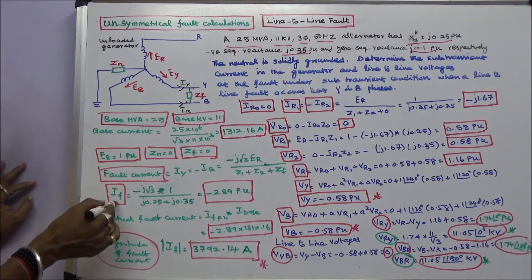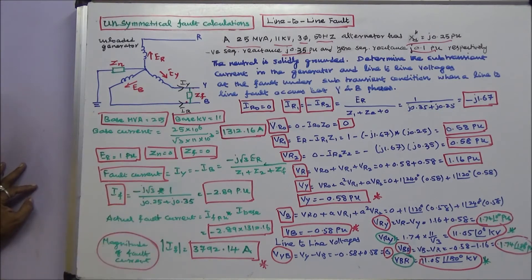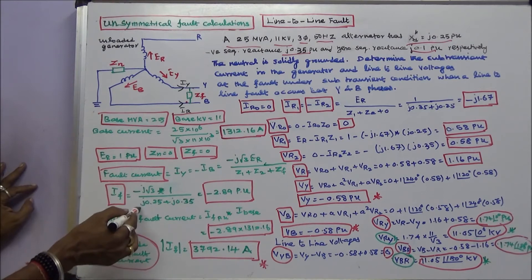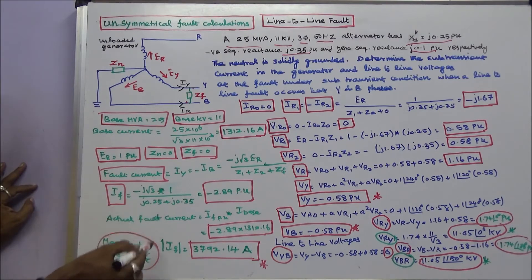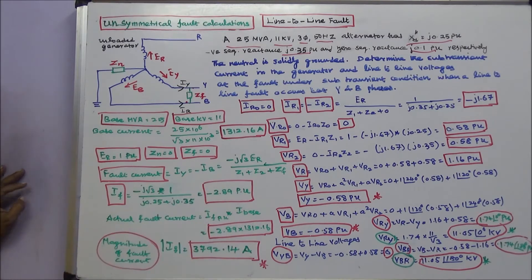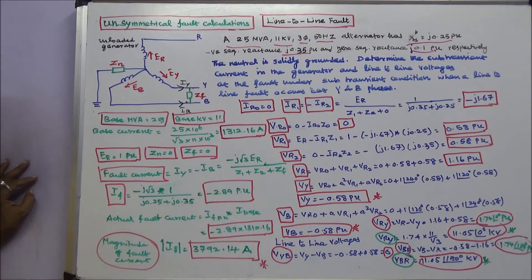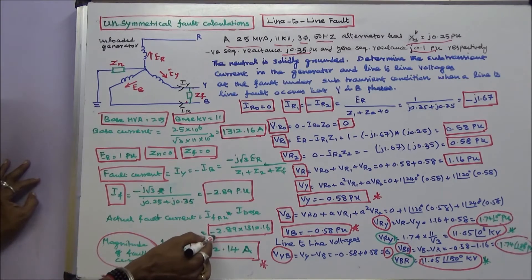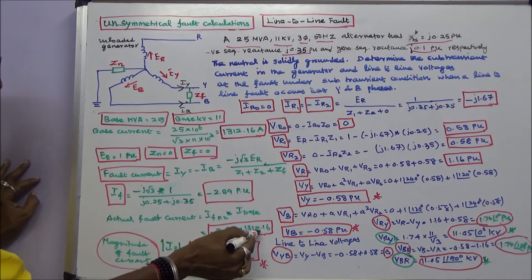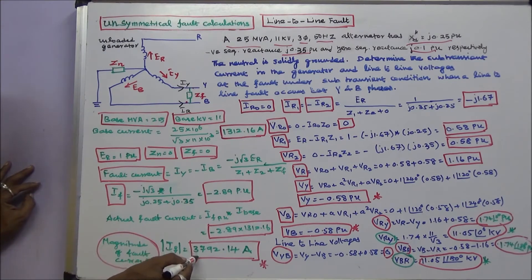So IF is equal to minus j into root 3 into 1, since ER is equal to 1. Positive sequence impedance is j0.25 and negative sequence impedance is j0.35. IF is equal to minus 2.89 per unit. Actual fault current is per unit current into base current: minus 2.89 into 1312.16. The magnitude of fault current is 3792.14 amps.